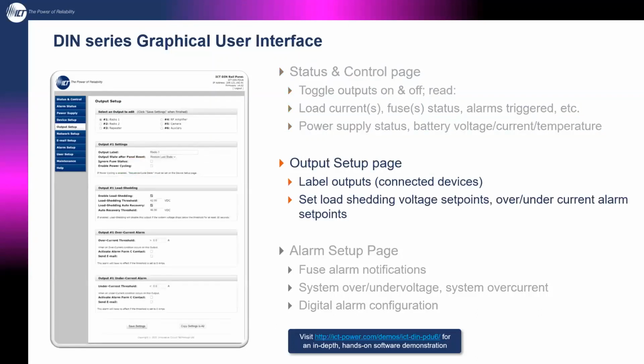Your voltage and current levels, along with the ambient temperature using a temperature probe, can all be done here. Another example: here's the output setup page, where you can name each connected device, set its values, the thresholds for disconnect or reconnect points. If you're in load shedding mode, where you're on backup batteries and the voltage is draining out, you can keep the critical loads up by disconnecting the secondary or tertiary loads, however you've categorized them, and have them disconnect at X voltage and reconnect at Y voltage when power comes back and the battery charges up.